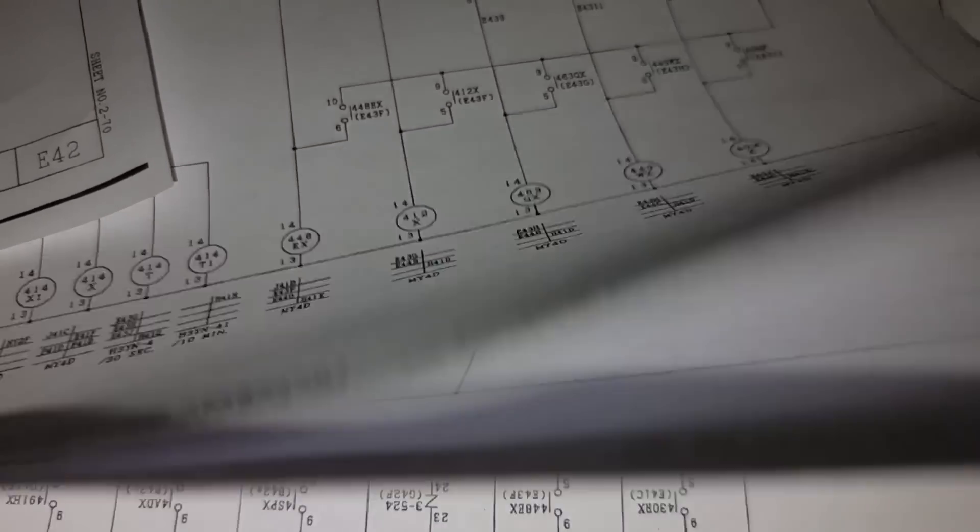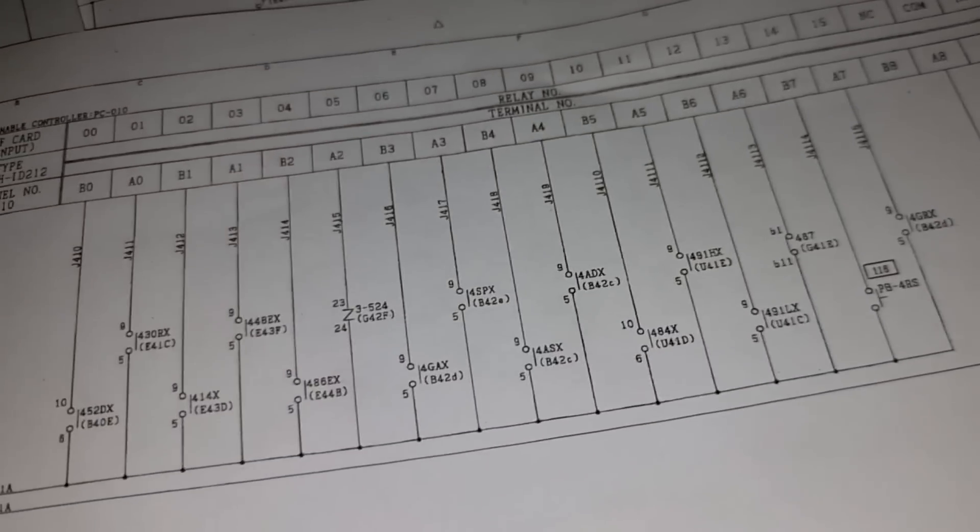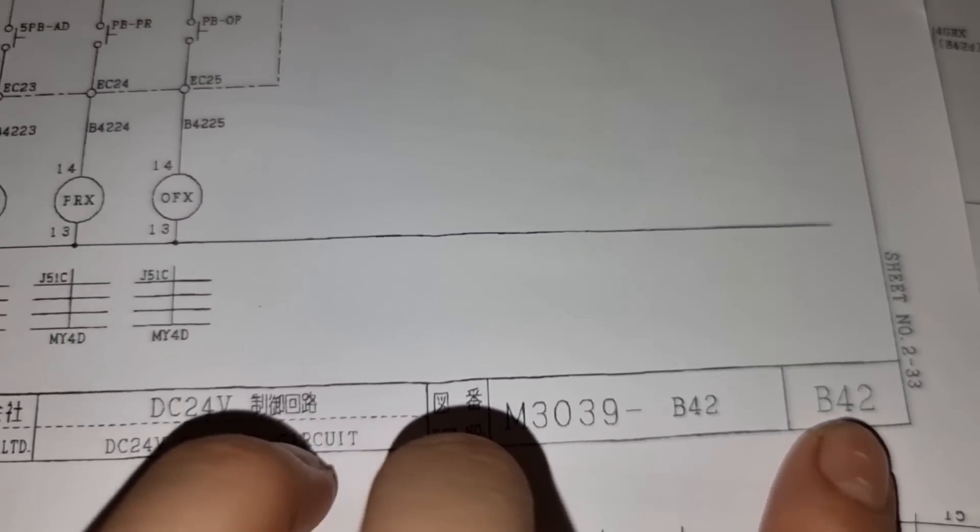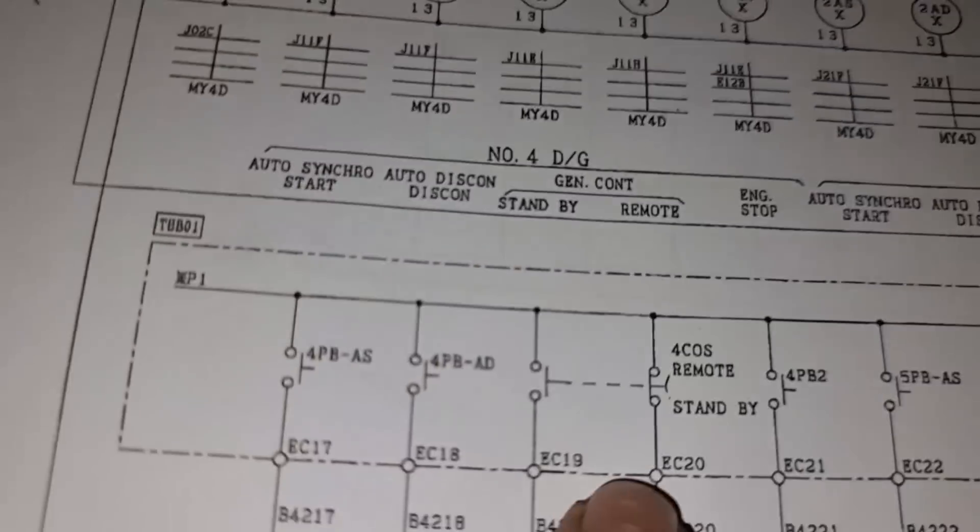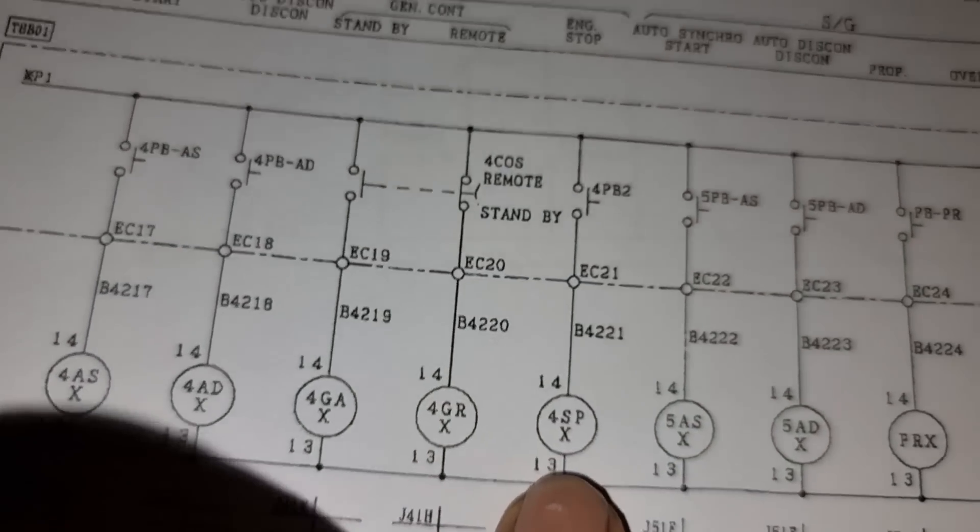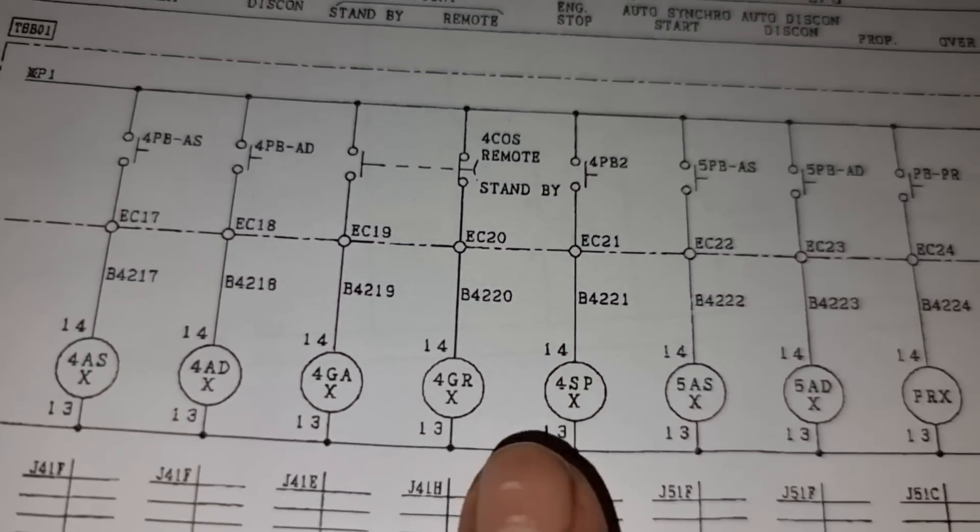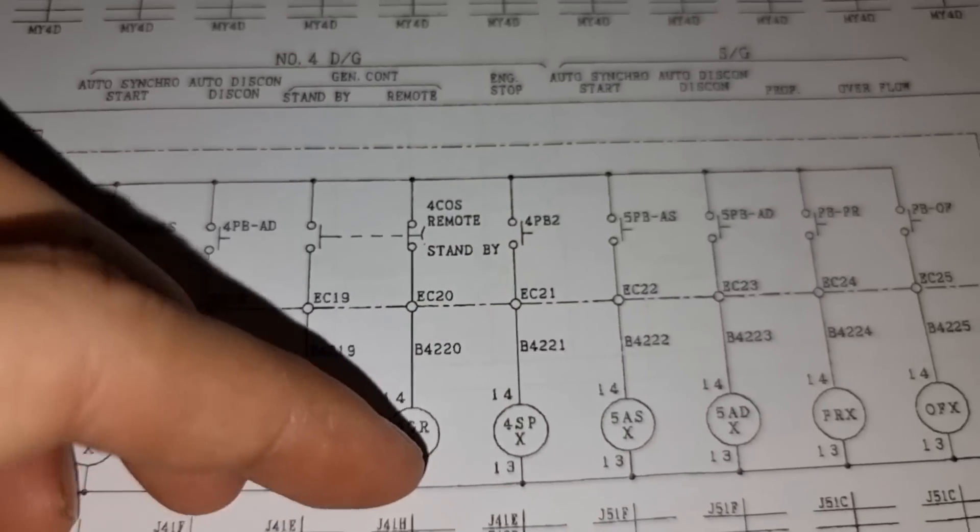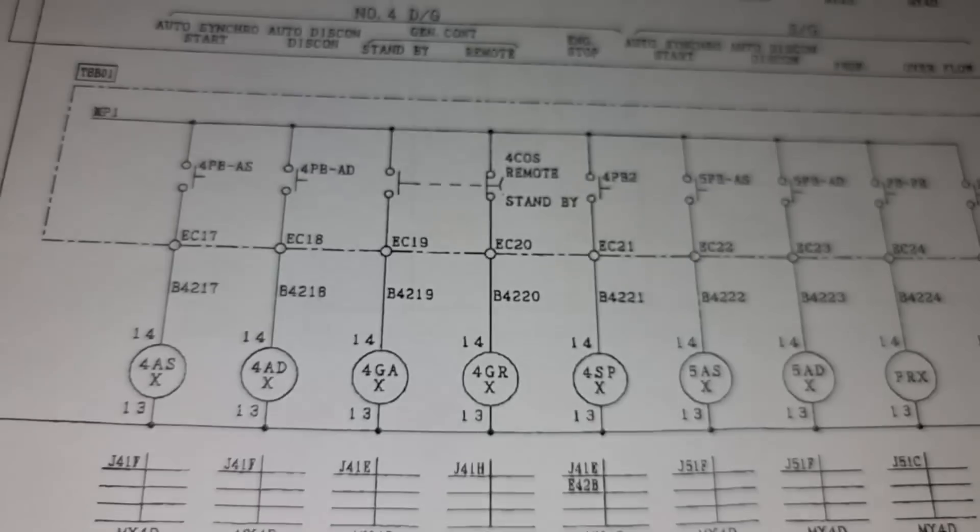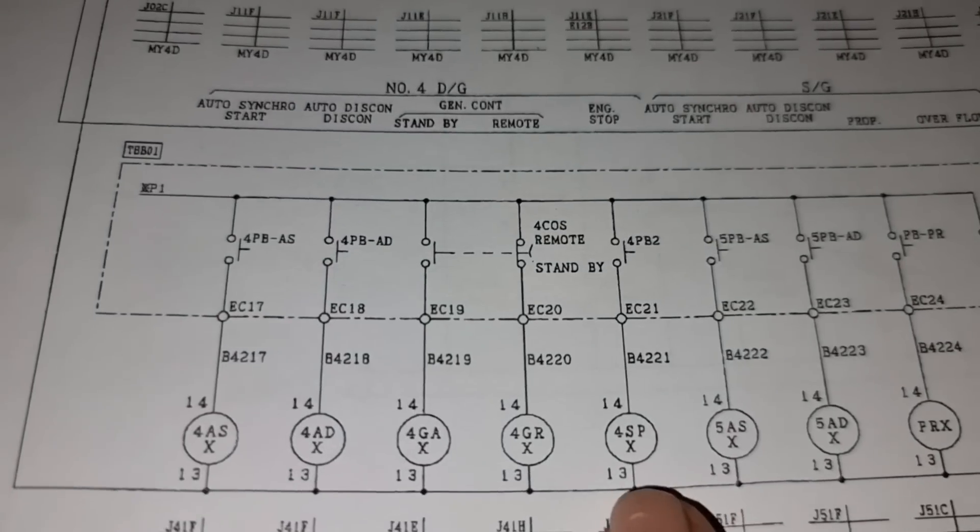And we need to check this B42E page. And the B42E page is this B42E and then this 4SPX. And this is the engine stop for the generator. And then this 4SPX, we need to check now if we have voltage on 13 and 14. This is also a 24 volts supply.